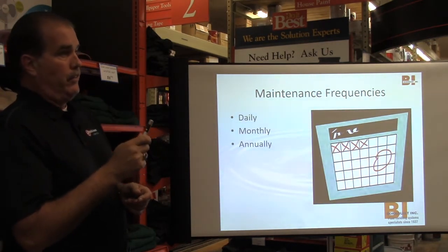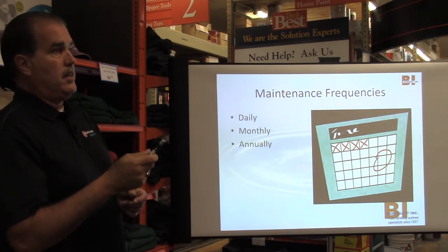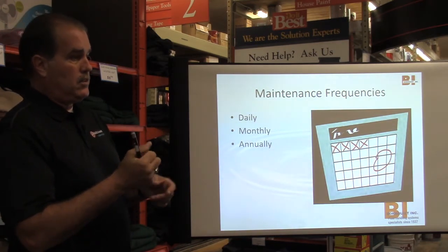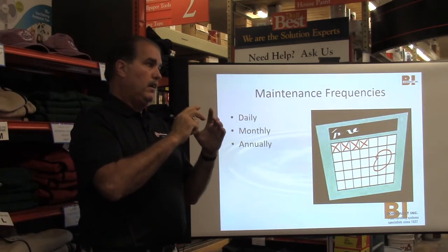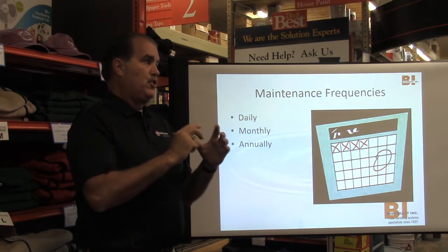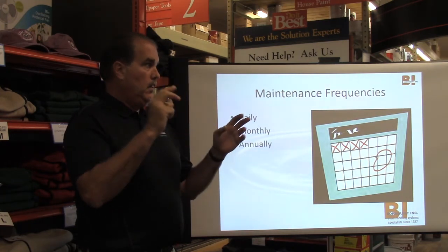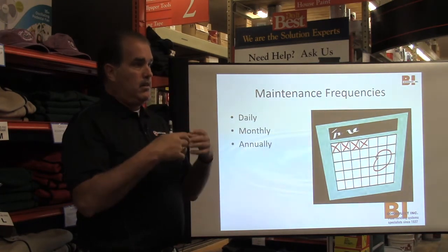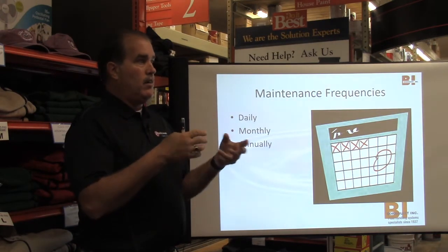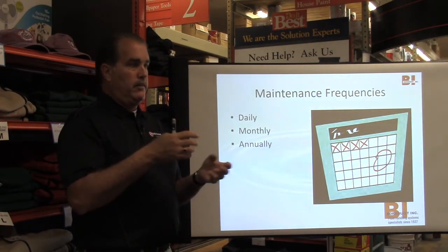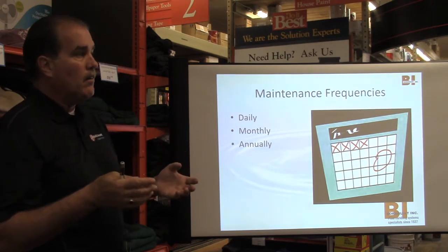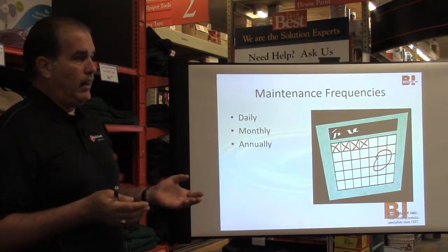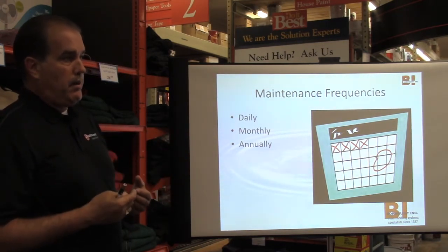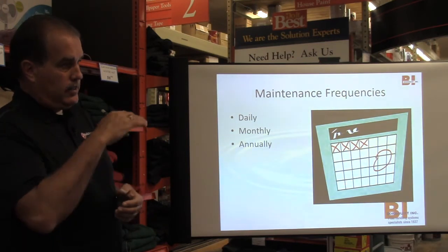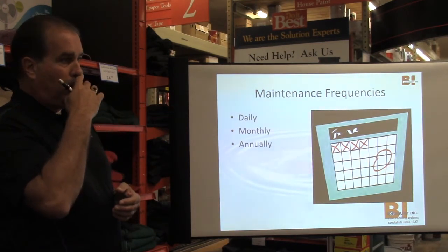You want to skim the boiler first. I don't know if you've ever heard of skimming. Basically, there's a pipe on that steam boiler. When the guy first installed it, he put all this new pipe in there. He cut pipe, and all these cutting oils and debris and flux or whatever are all in that water. You can't get it all out, and it's going to work its way back to the boiler eventually. That gets on the water line, but typically it'll float.